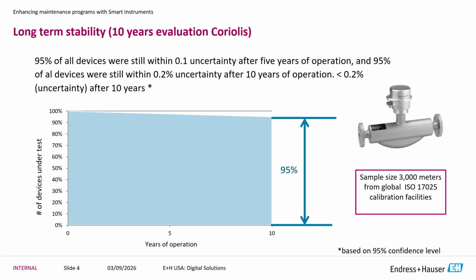So the fact is, Coriolis is very stable, but yet we calibrate it every 6 months, 12 months, and we actually introduce, and we can prove this, we introduce more risk touching it, removing it, putting it up on our rig, doing the calibration, reinstalling it. We know that this actually brings in more risk than just leaving it. The 0.2% after 10 years is proven. So we do have this study that we provide for data set.